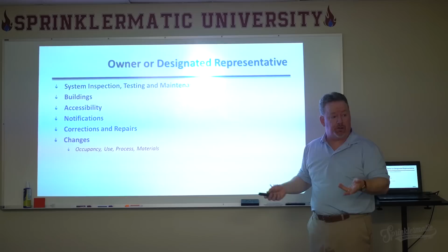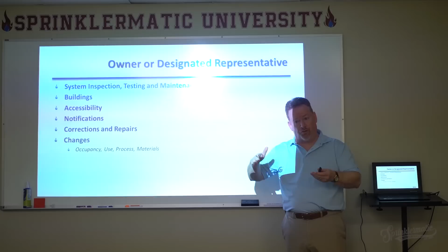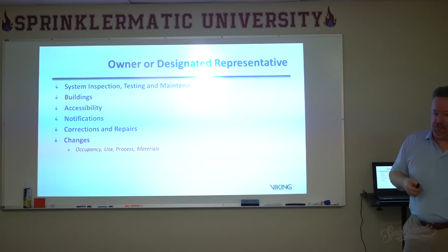So when we take a look at the owner's responsibilities in particular, there's a lot of detail in this. It's in chapter 4 of NFPA 25, which contains the details for what the responsibilities are for the owner, or what's called his designated representative. The designated representative can be anybody, like a property manager, or it could be the tenant of the building, based on their lease agreement, that all of a sudden becomes responsible for maintaining systems. When we look at chapter 4 and the responsibilities of who's responsible for this system as far as NFPA 25 is concerned, the owner or designated representative has a lot of details here that they're responsible for.